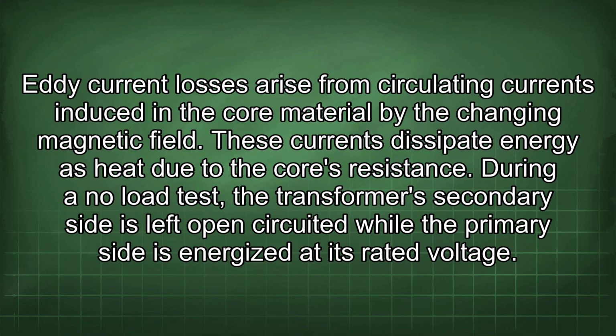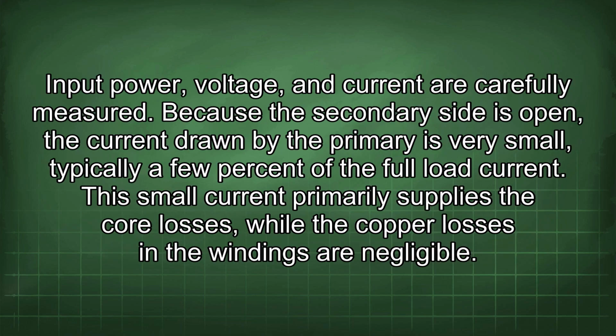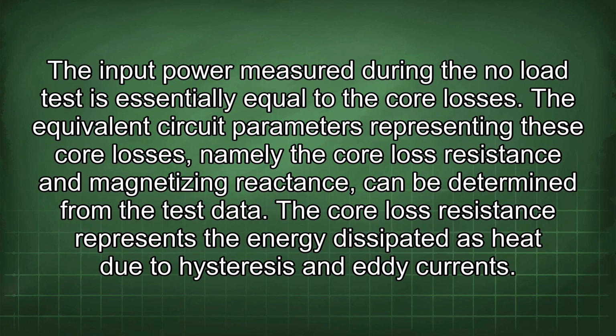During a no-load test, the transformer's secondary side is left open-circuited while the primary side is energized at its rated voltage. Input power, voltage, and current are carefully measured. Because the secondary side is open, the current drawn by the primary is very small, typically a few percent of the full load current. This small current primarily supplies the core losses, while the copper losses in the windings are negligible. The input power measured during the no-load test is essentially equal to the core losses.